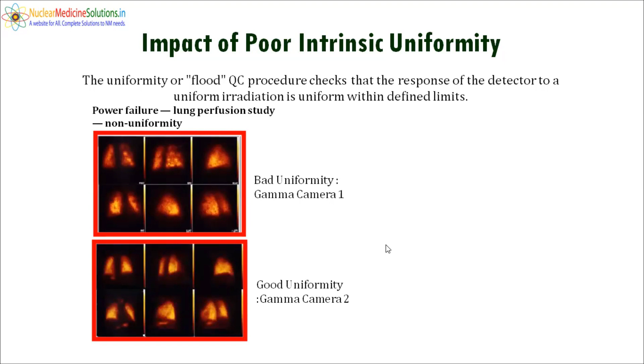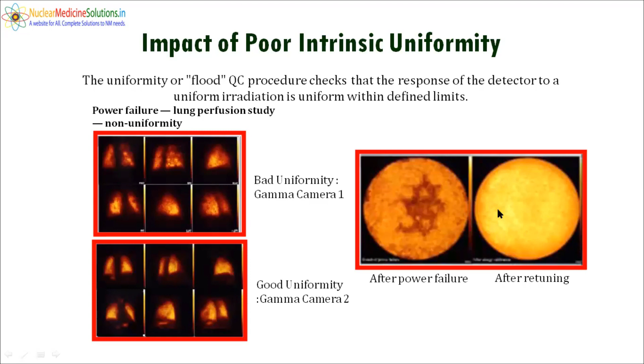When we performed the uniformity test of this gamma camera, we found the uniformity was worst. So we performed the PMT tuning, and after the PMT tuning, we again performed the uniformity test of gamma camera 1, and this time it was okay. So PMT tuning also affects your uniformity.